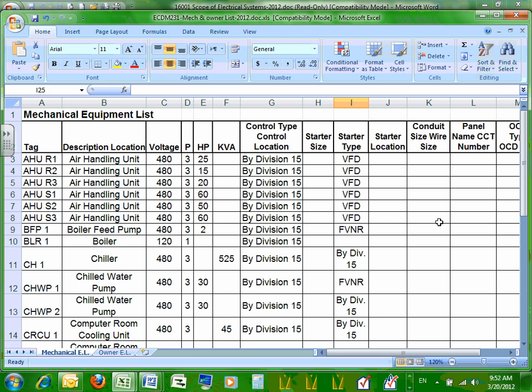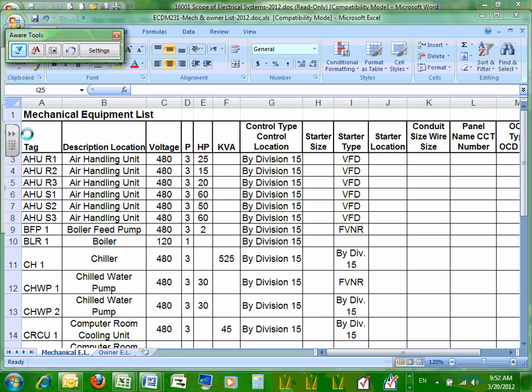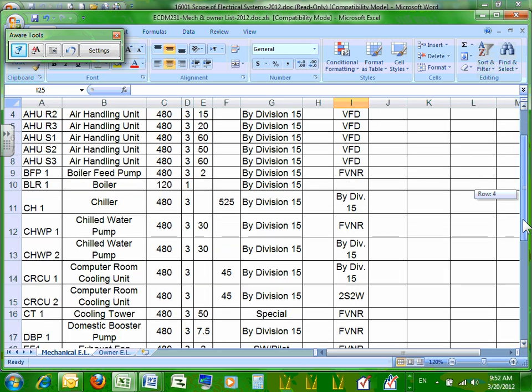And we have done that on a number of our bigger projects where it's 50 to 500 horsepower motors kind of lined up. Now we need a specialty tuned harmonic filter next to the VFD to minimize the reflection of harmonic currents back into our building system, because the VFD is a kind of harsh nonlinear load that reflects harmonics back into our system. And so again, I'm of the strong mindset that when electrical specifies the VFDs, we pay more attention, and we can better understand the impact of those drives in our system. And so those would be by the electrical contractor.